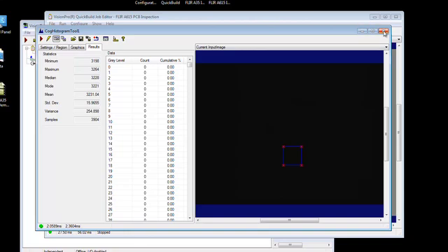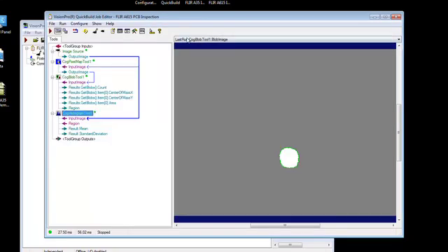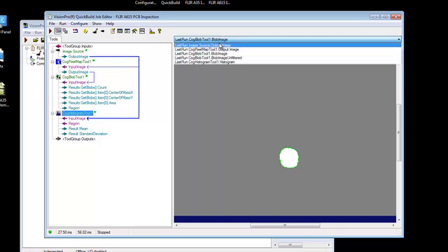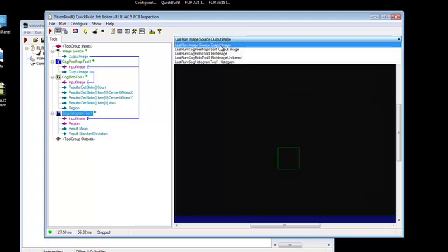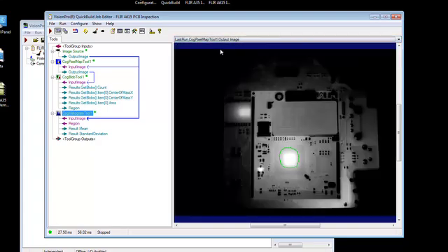So the temperature linear data output of a FLIR camera is what makes it truly plug and play with VisionPro software. You simply add in the object parameter values for your given camera, let the FLIR camera calculate the measured temperature values, and display that on your 2D 16-bit video output from the camera.